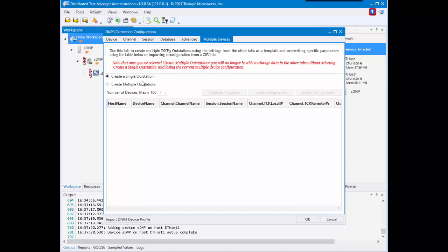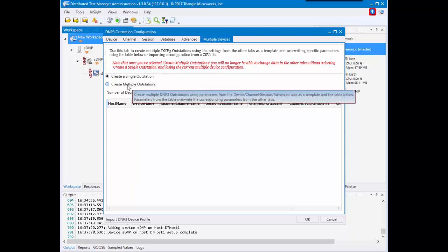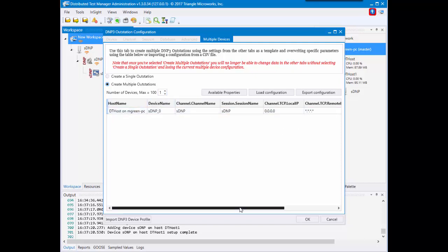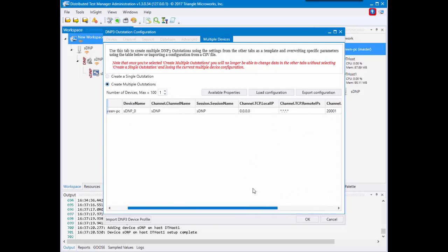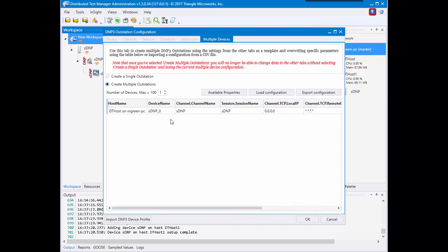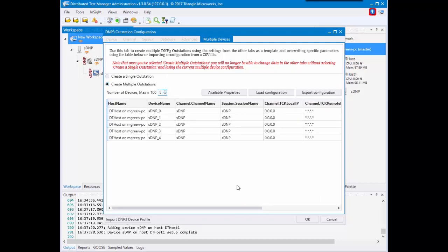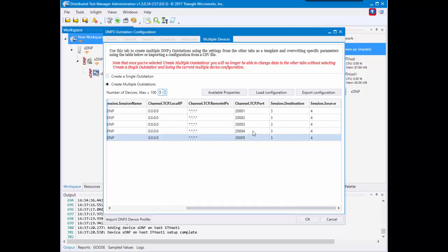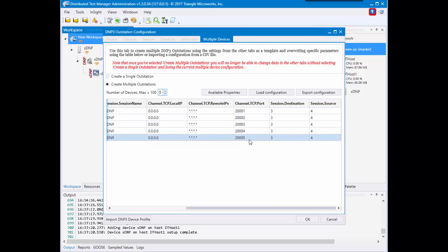From here you would select create multiple outstations and you'll see it defaults to one and that's the configuration information for our first DNP outstation. For this configuration you can increase this and you'll create more instances of the device. As you can see here, by default we increase the port number to make sure they all have unique configuration information.